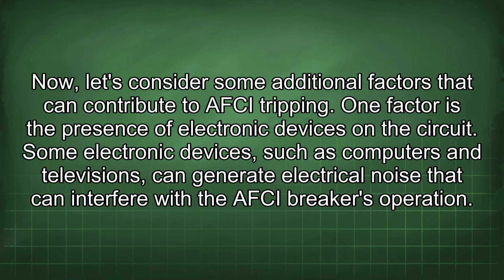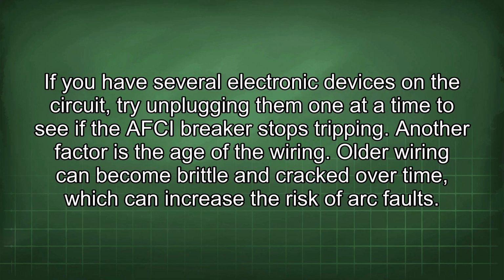Now, let's consider some additional factors that can contribute to nuisance tripping. One factor is the presence of electronic devices on the circuit. Some electronic devices, such as computers and televisions, can generate electrical noise that can interfere with the AFCI breaker's operation. If you have several electronic devices on the circuit, try unplugging them one at a time to see if the AFCI breaker stops tripping. Another factor is the age of the wiring.